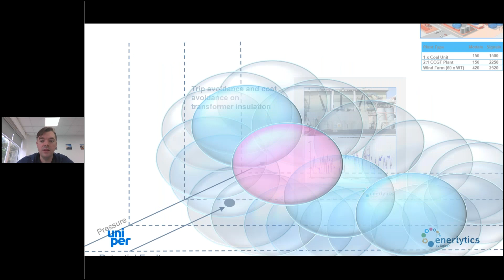This is a transformer that had a safety cordon around it. The regulator identified a design fault that effectively meant we must put a safety cordon around it, and that meant the routine maintenance stopped. However, we detected an increase in winding temperatures outside what we considered good operation. So the actuals had moved outside the sphere, and we spoke to the site and said, look, we know about the environmental and the regulatory permit, but you're actually getting an increase in winding temperatures, so you should perform your routine maintenance, meeting the risk assessment. So the permit was raised, the risk assessment was completed, and the site went and cleaned debris, leaves, mud, and waste off the top of the transformer, and that dropped the temperatures back down to what was expected.